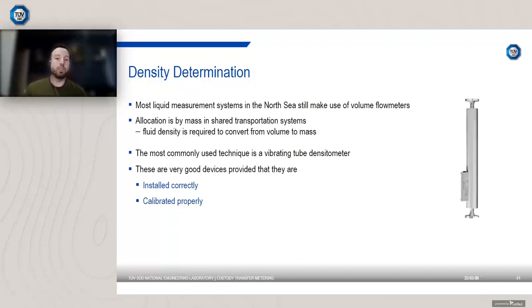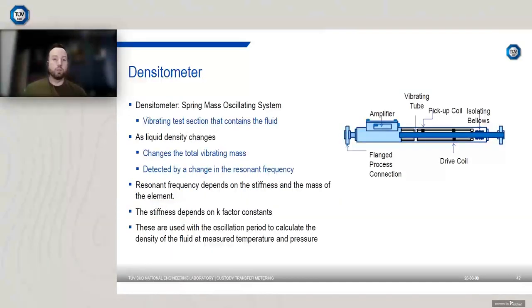The most commonly used technique is a vibrating tube densitometer, and these are very good devices provided that you've installed them correctly and calibrated them properly. So how does a vibrating tube densitometer work? It's very similar to the way the Coriolis meter measures density. You've got a vibrating test section that contains your fluid, and as the liquid density changes, this changes the total vibrating mass. And how do you detect that? You can detect it by a change in the resonant frequency. So you measure the frequency.